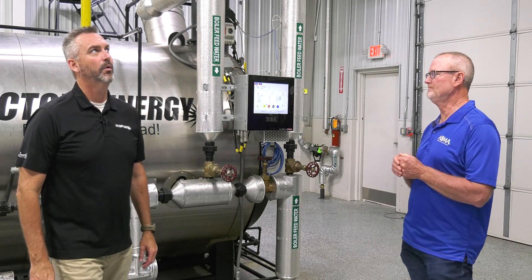Is it actually the boiler that's causing that? What causes that? No, it's the stack. We run into it because we design them in on new installations, so we know what's going on. We'll design the stack and put dampers in if we have to. What we run into it more is on burner conversions, where it's an existing burner. They've got a stack that's 40, 50 feet high. And with that tall stack, as soon as you start firing, it actually creates its own draft. So it starts sucking air through the boiler, and the next thing you know, you've got a negative draft. So it's pulling the flame off the burner.